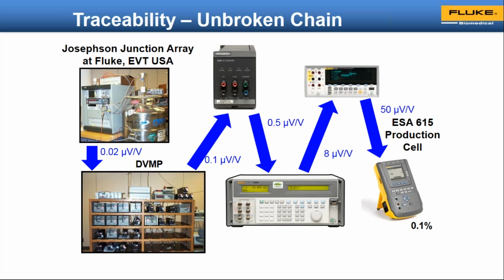So we go from the DC volt primary to a transfer standard, and you can see that we add some uncertainty at every step. From 0.02 microvolts per volt, for example, by the time we have transferred this in and done the calibration around DC volts in something like our electrical safety analyzers that you are using, our uncertainty is 50 microvolts per volt. So there's been an increase in our uncertainty simply because we're transferring that volt. And you can see that our accuracy confidence here is that we're accurate to within 0.1%. So it's very easy to see how we transfer that through our production line and also through our recal.